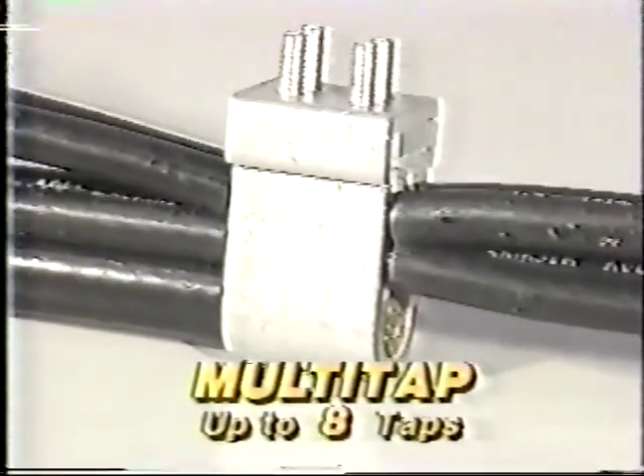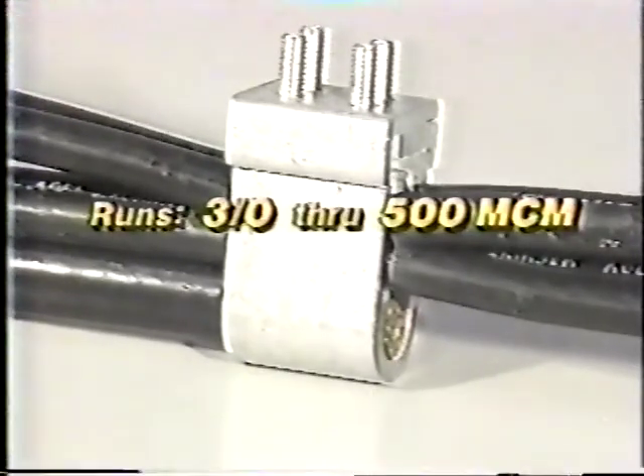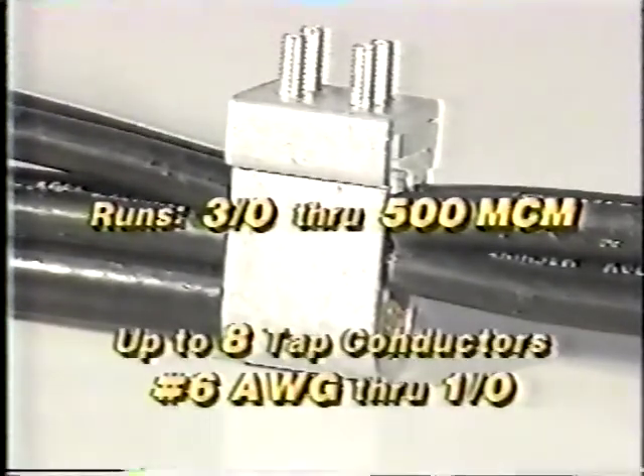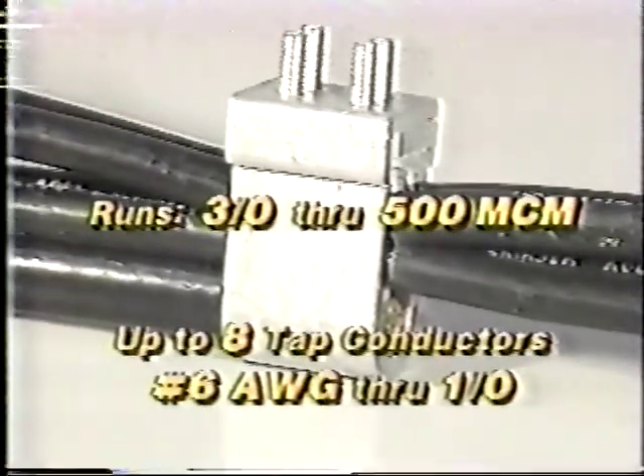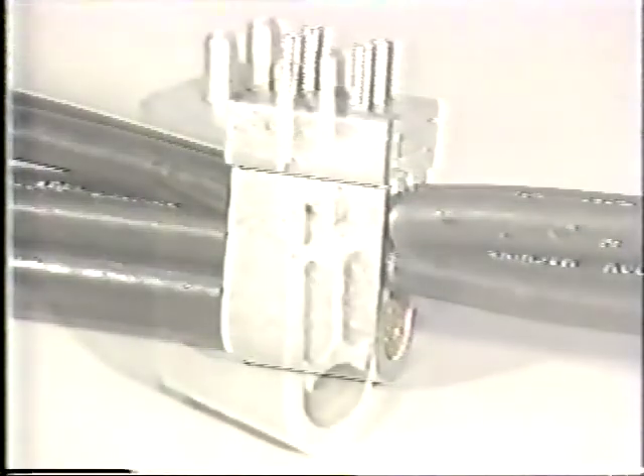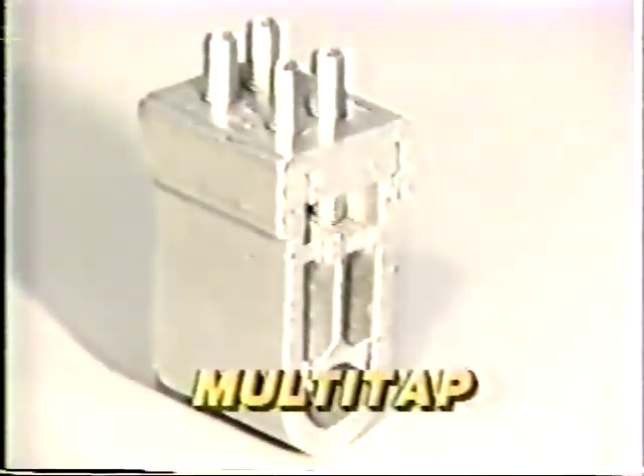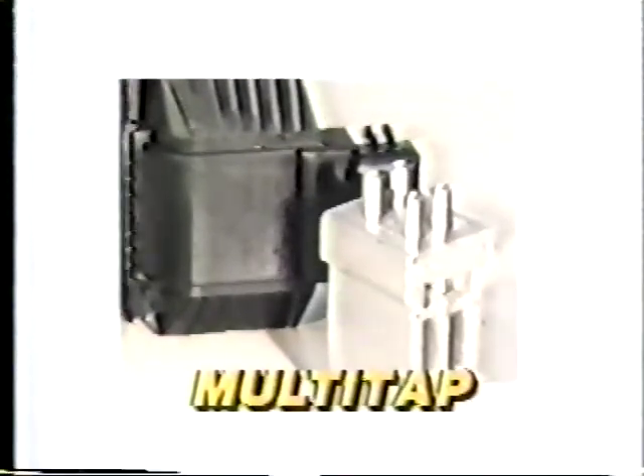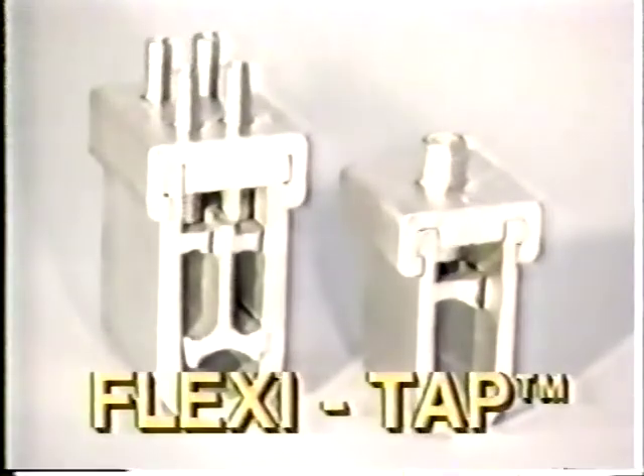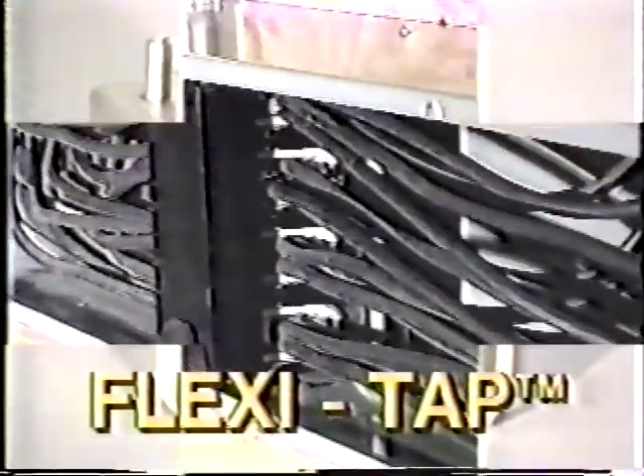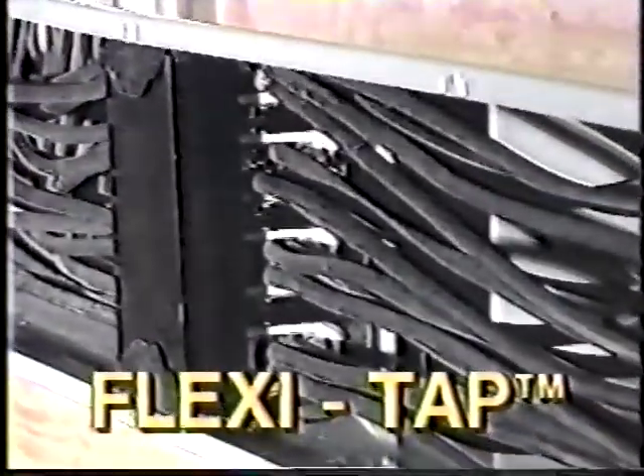Just one multi-tap connector will accommodate runs ranging from 3/0 through 500 MCM and up to 8 tap conductors ranging from number 6 through 1/0. As with our basic U-Tap, the multi-tap version is low in cost and features an optional snap-on insulating cover. U-Taps are only the beginning of Burndy's FlexiTap system. This state-of-the-art system carries the basic U-Tap features throughout a family of power distribution connectors.